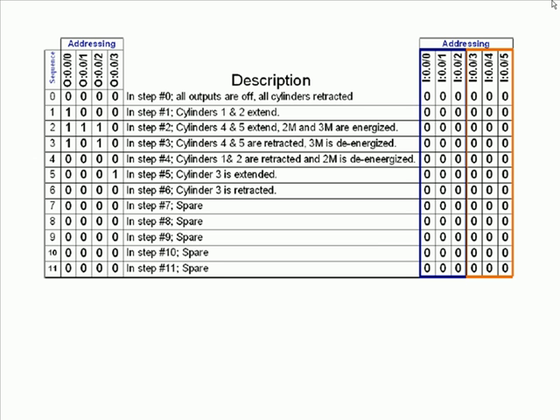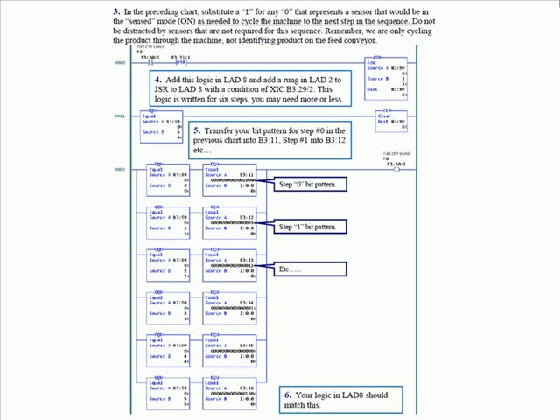You see in step one for the outputs it says cylinders one and two extend — well, we don't extend them until the photo eye sees the part there in front of cylinder two. So you'll have to add that in at some point — the product recognition which is required to go to the next step. So all you do here was go in and change the zeros to ones that represented the result of the motion caused by the outputs that were energized in the same state.